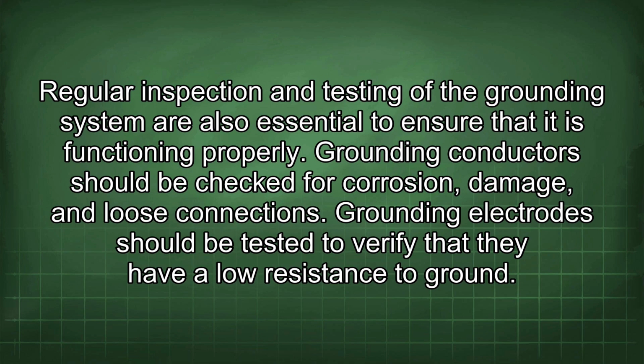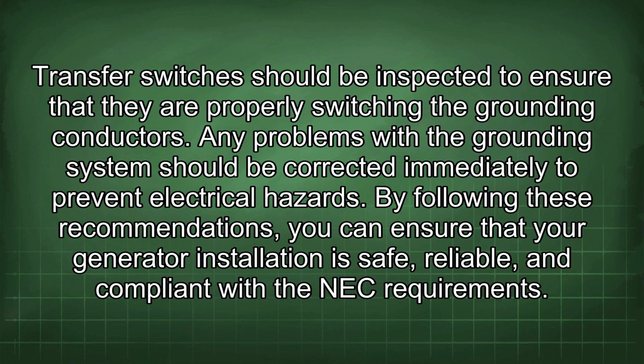Regular inspection and testing of the grounding system are also essential to ensure that it is functioning properly. Grounding conductors should be checked for corrosion, damage, and loose connections. Grounding electrodes should be tested to verify that they have a low resistance to ground. Transfer switches should be inspected to ensure that they are properly switching the grounding conductors. Any problems with the grounding system should be corrected immediately to prevent electrical hazards. By following these recommendations, you can ensure that your generator installation is safe, reliable, and compliant with the NEC requirements.